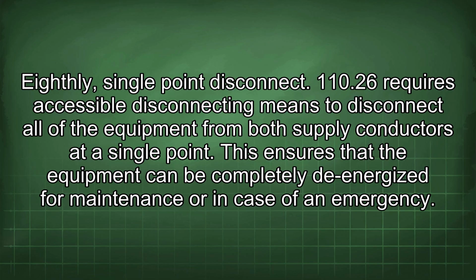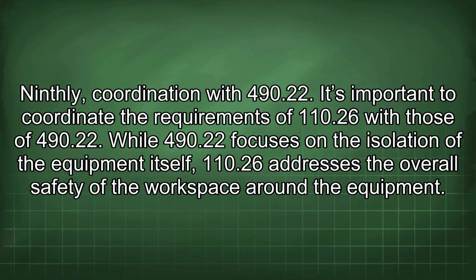Eighthly, single-point disconnect. 110.26 requires accessible disconnecting means to disconnect all of the equipment from both supply conductors at a single point. This ensures that the equipment can be completely de-energized for maintenance or in case of an emergency.